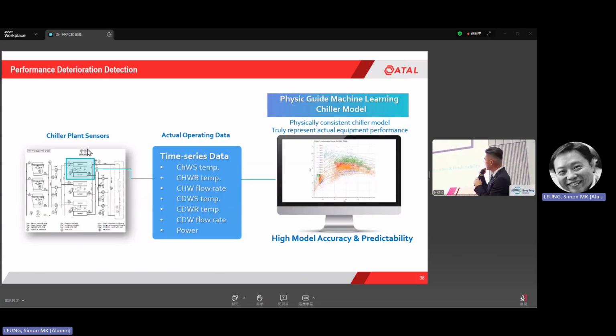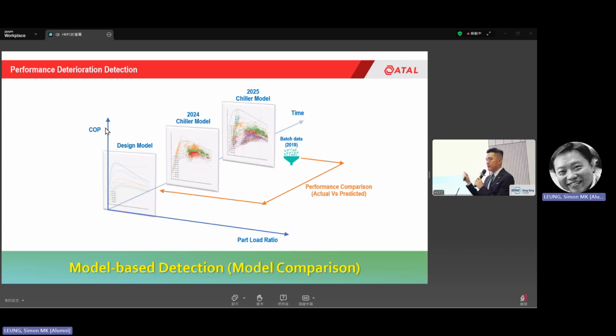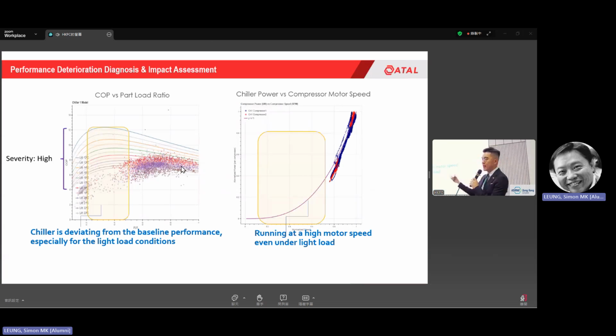So as I said, we have the data, we can do the machine learning. That means it can capture the characteristics of the performance. Then we can compare it monthly or annually to see whether there is a deviation. This is an apple-to-apple comparison. So for this example, we can see that for the low-load condition, it deviates from the baseline performance. That means something is wrong with this asset, and we need to do the maintenance. If the performance is the same as the baseline performance, then in theory we do not need to do the maintenance because it provides the same energy use under the same condition.